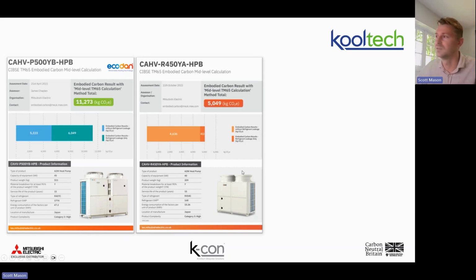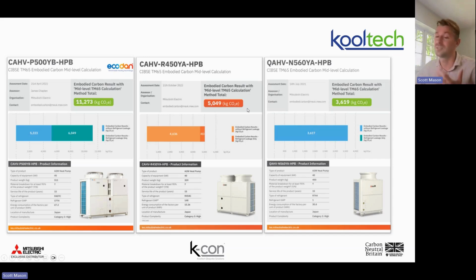So massive difference. And then that brings us on to the QAHV. The QAHV is a hot water only unit. Where we've got an application which is heating and hot water and the two are separated out, we always lead with the QAHV for hot water. And the reason is CO2 units need a cold return temperature. On a hot water application, I can guarantee a cold return temperature because my cold feed is going to come in at 10 degrees centigrade. So what a lovely way to use it and apply it.